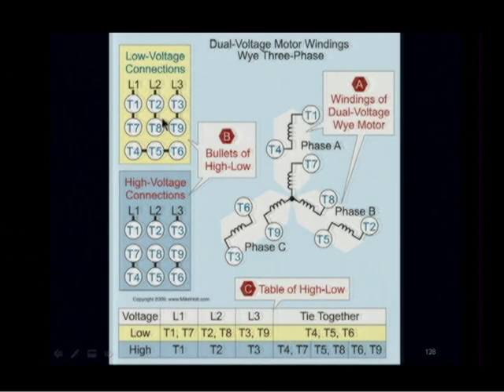Why it's a Y, obviously it has to do with design, and there are things beyond the scope of this control class that we have to worry about, but we're trying to help somebody know how to hook up the motor. In other words, you can't go to this wiring configuration and think that applies to all motors. You've got to go to the nameplate and hook it up according to the nameplate and not worry about what's going on internally.